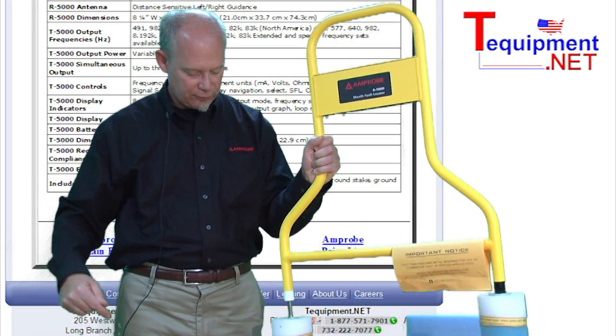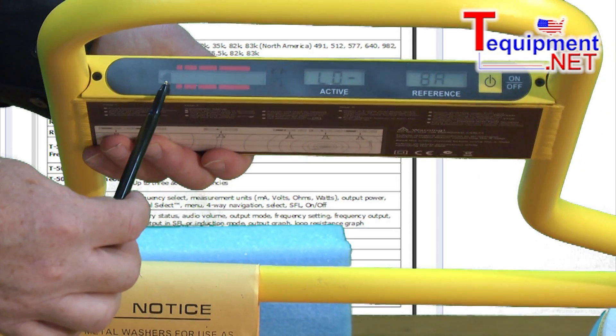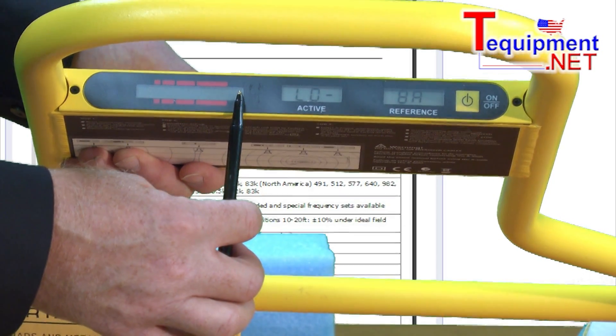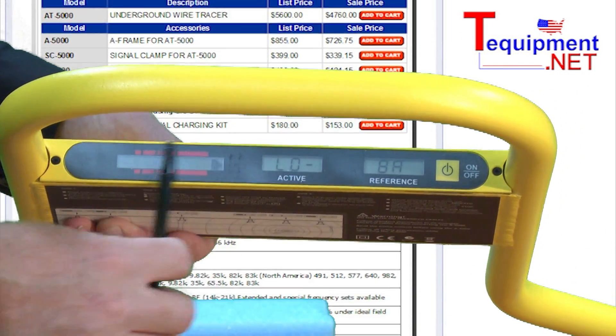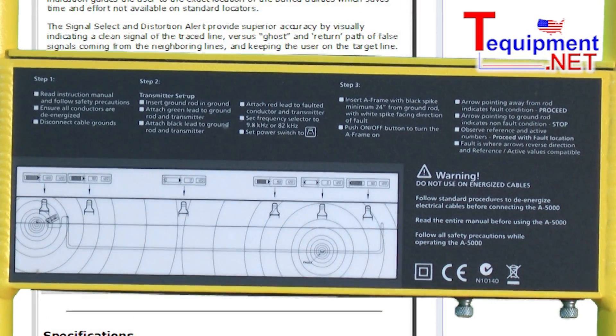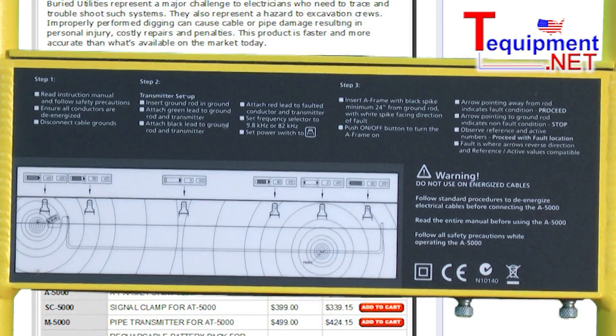We have two different modes of operation. Arrows will indicate where we are relative to the fault. This is telling us that the transmitter is in this direction. When the arrow is over here, it tells us we're moving away from the transmitter, and then if this fills up with all black lines, that tells us we're right on the fault. On each of the pieces, the directions are right there on a decal, and right on the instrument it shows us how to use it.